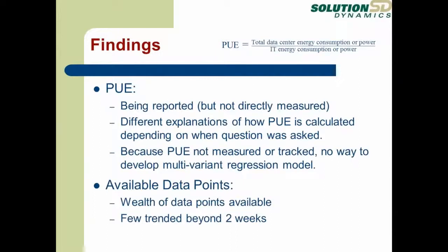And granted, this is a company that cares about PUE, and this is a very large data center which has electrical costs approaching $1 million a month. They had a tremendous wealth of data points available. However, very few were being trended beyond 2 weeks. So they had the information, but they weren't necessarily utilizing it.